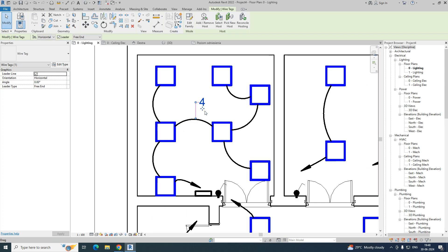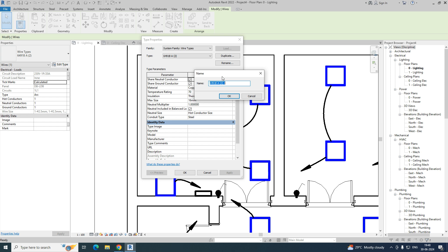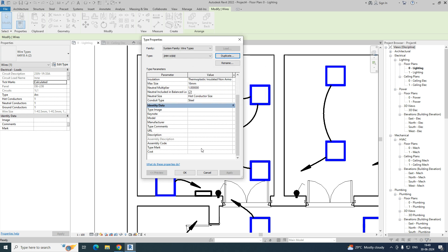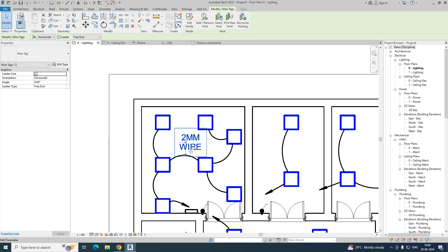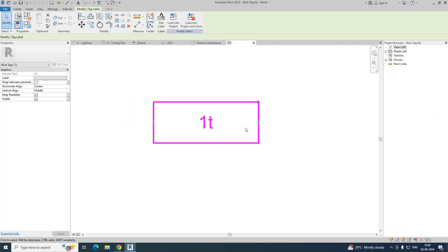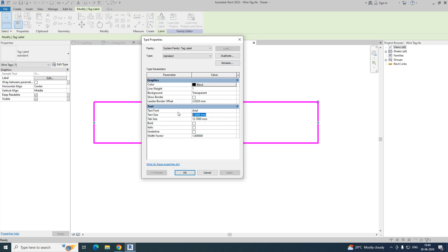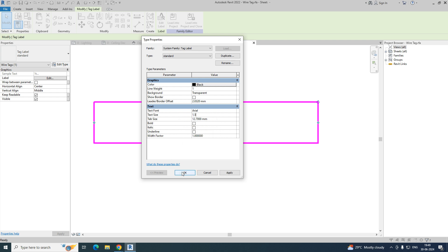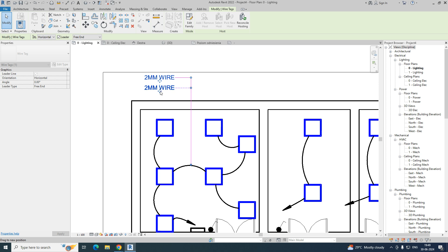Select the wire and go to Edit Type. You can duplicate it — for example, '2mm' wire size. Click duplicate and give it a name, then add a type mark and click OK. Now you can see the wire size is showing. If you want to expand the tag, select and stretch it. You can also change the text size — for example 1.5 — as per your drawing standard. Then load it back.